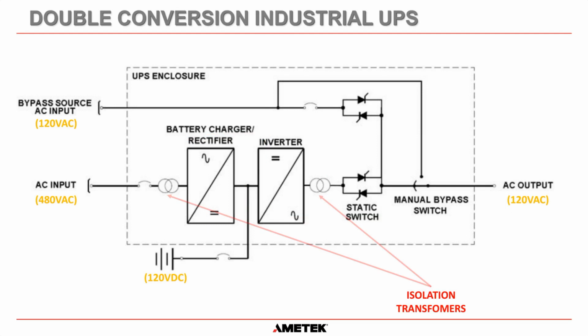And for an industrial UPS, one of the big differences between a commercial UPS and an industrial UPS is that you should see isolation transformers on the input and on the output. Because what we have in here is a DC bus. And if you have any kind of failure in the battery charger rectifier that allows DC to get back onto the AC, that could cause havoc on all the loads fed from your MCC and would cause a huge amount of issues inside the plant.